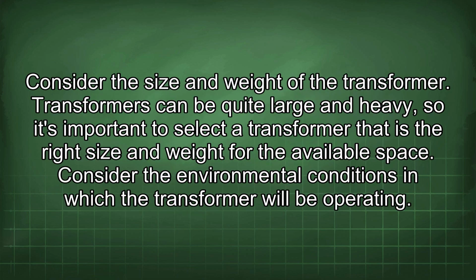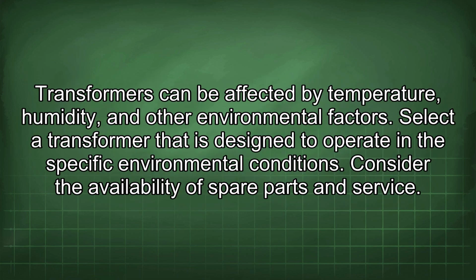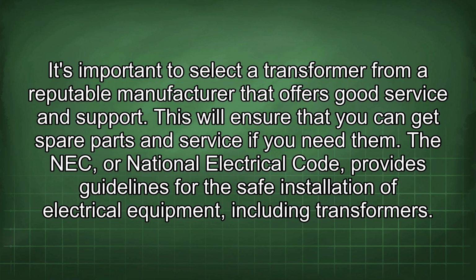Consider the size and weight of the transformer. Transformers can be quite large and heavy, so it's important to select a transformer that is the right size and weight for the available space. Consider the environmental conditions in which the transformer will be operating. Transformers can be affected by temperature, humidity, and other environmental factors. Select a transformer that is designed to operate in the specific environmental conditions. Consider the availability of spare parts and service. It's important to select a transformer from a reputable manufacturer that offers good service and support. This will ensure that you can get spare parts and service if you need them.